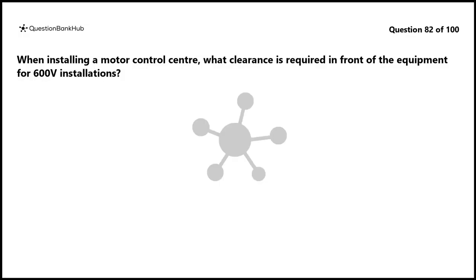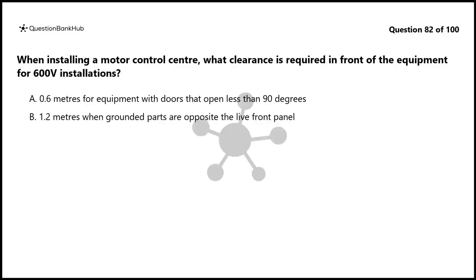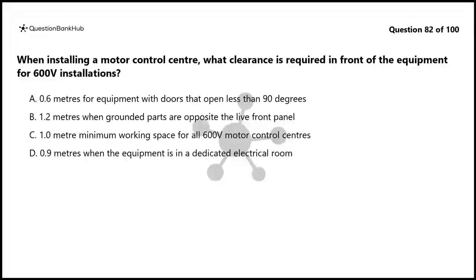Question 82. When installing a motor control center, what clearance is required in front of the equipment for 600 volt installations? A. 0.6 meters for equipment with doors that open less than 90 degrees. B. 1.2 meters when grounded parts are opposite the live front panel. C. 1.0 meter minimum working space for all 600 volt motor control centers. D. 0.9 meters when the equipment is in a dedicated electrical room.